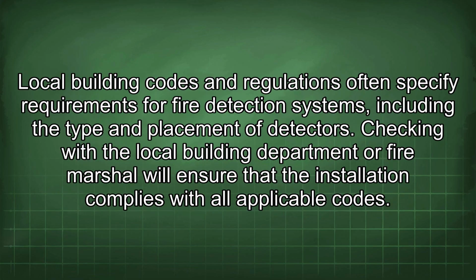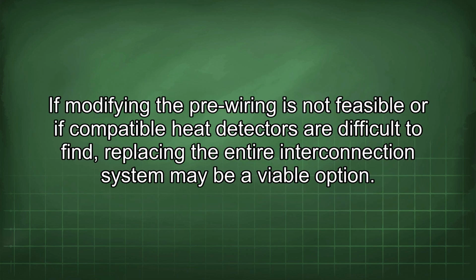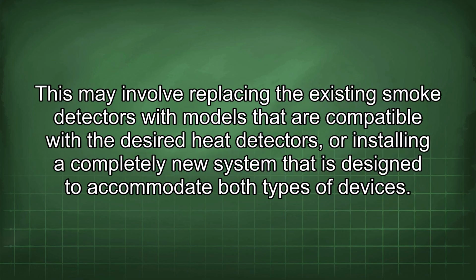Local building codes and regulations often specify requirements for fire detection systems, including the type and placement of detectors. Checking with the local building department or fire marshal will ensure that the installation complies with all applicable codes. If modifying the pre-wiring is not feasible or if compatible heat detectors are difficult to find, replacing the entire interconnection system may be a viable option. This may involve replacing the existing smoke detectors with models that are compatible with the desired heat detectors, or installing a completely new system that is designed to accommodate both types of devices.